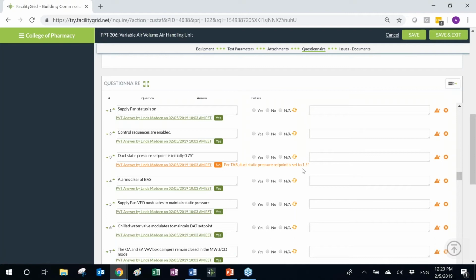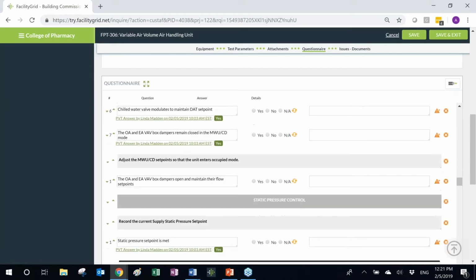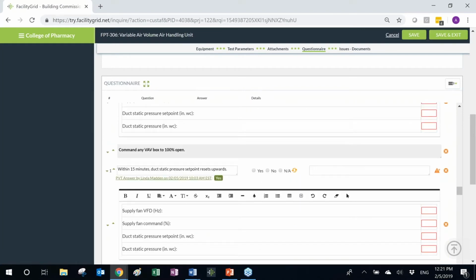Again, when I'm performing the test as a commissioning agent, I have all this information in front of me. I don't have to search. I don't have to guess what the actual value is supposed to be. Again, I can verify it by looking at the testing and balancing report, but I know at least the controls contractor indicated what has been programmed in the BAS and what data is actually in the program.